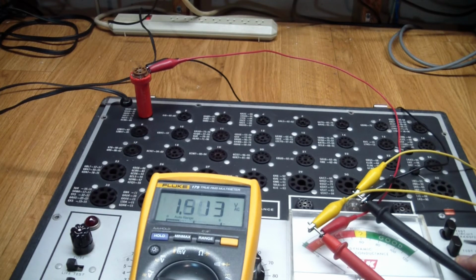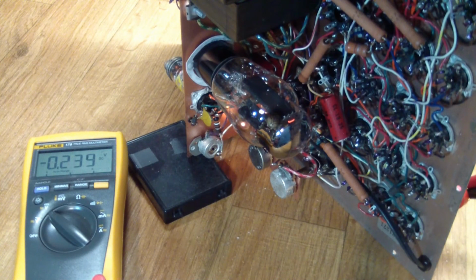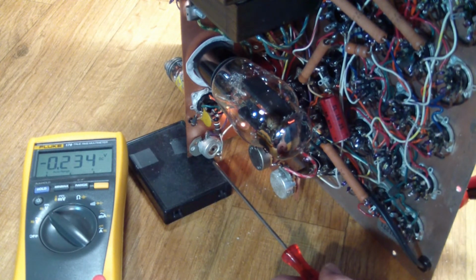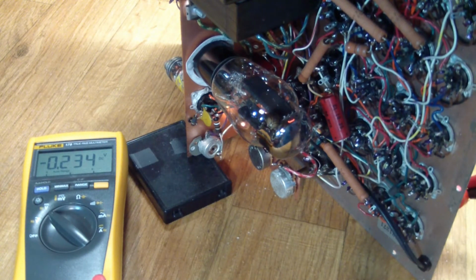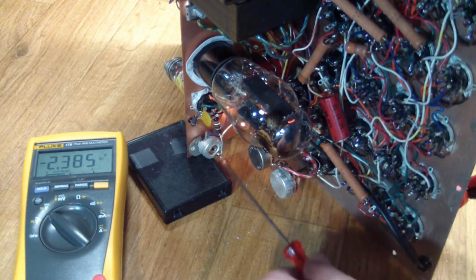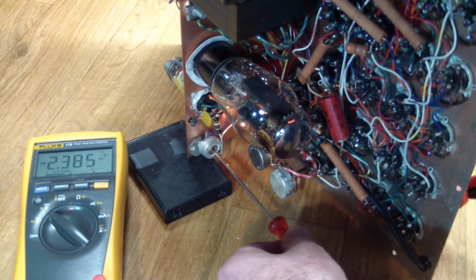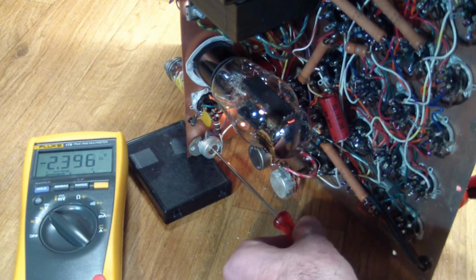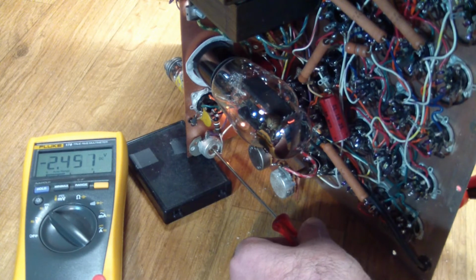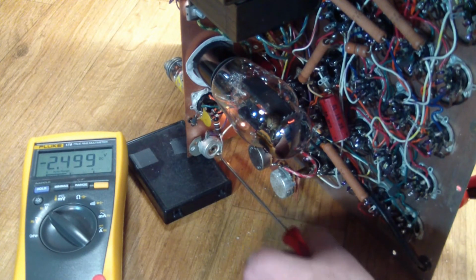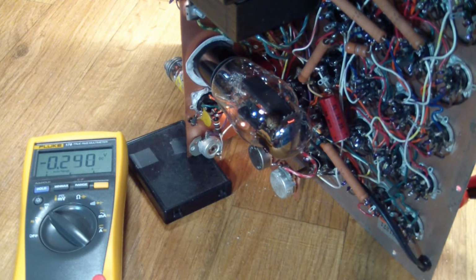And again, that's right on. So in order to reach pot R11, I had to take it out, put it on its side, and R11 is here. No more convenient access through a tube socket. But pressing the test 1 button still gives us the 2.3 something reading, and let's adjust this to the prescribed 2.5, and there you go.